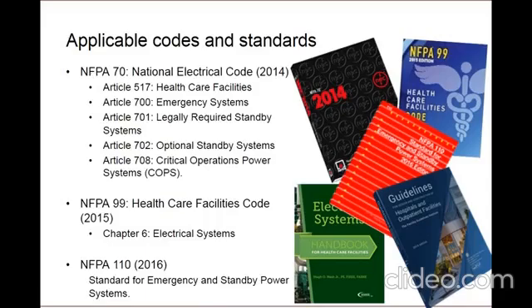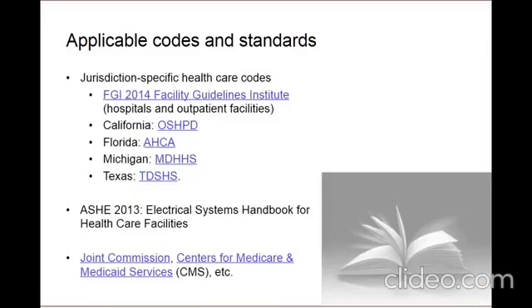And then you have NFPA 110, which is the standard for emergency and standby power systems. This code focuses at the source equipment and provides specific design, installation, and testing requirements of the main emergency power supply system. Once you digest the NFPA code requirements, there are additional standards that you must follow, including those adopted by state and local health departments. First off, you will have the FGI, or the Facilities Guideline Institute for Hospitals and Outpatient Facilities. While this is called a guideline, many jurisdictions consider this to be the enforceable code. However, there are several state-specific codes, such as California, Florida, Michigan, Texas, just to name a few.